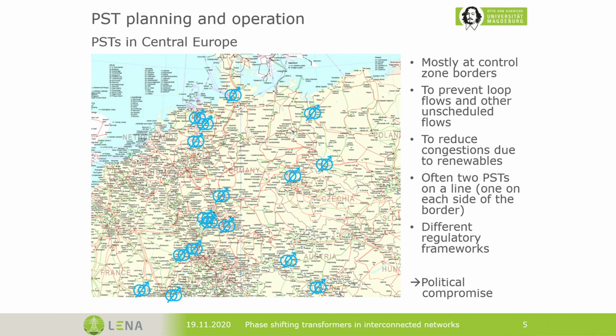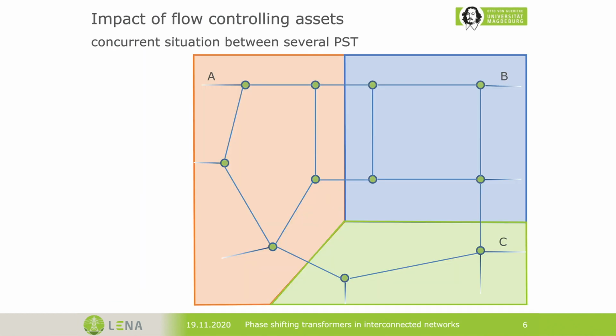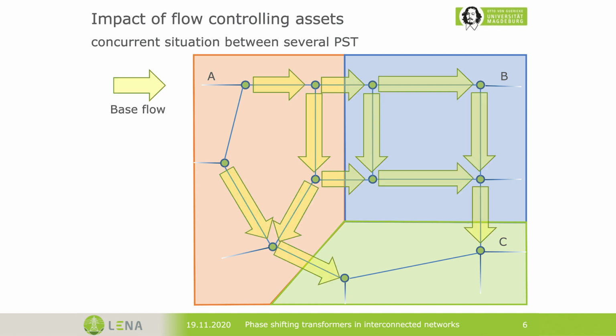So we positioned them at the borders of bidding zones, which are mostly the same as the borders of control zones in countries. So this is why it looks like that. From a technical point of view, this is probably not the best position for these PSTs, but it's a political compromise, so it works. Let's say there are 3 zones, A, B, and C, and let's imagine we have some power flow in this grid. And you can see in zone A there is some excess energy that is exported to the other zones B and C, and this will cause this base flow that is painted here in yellow.